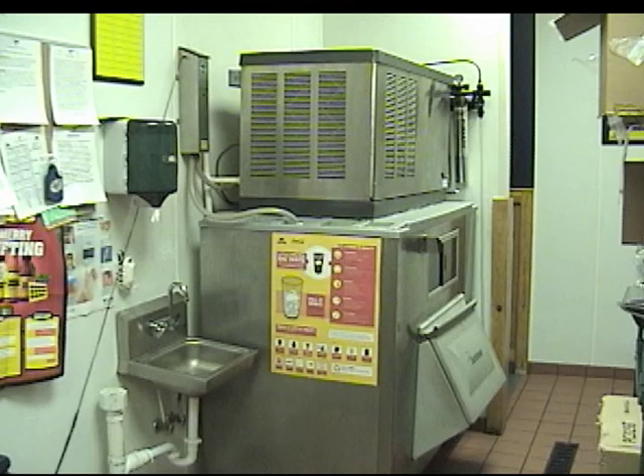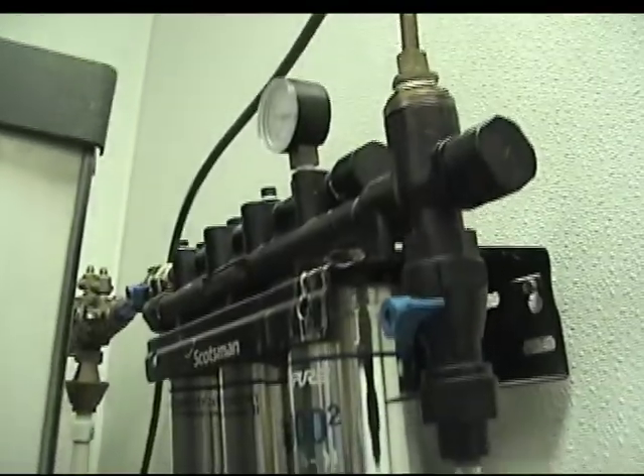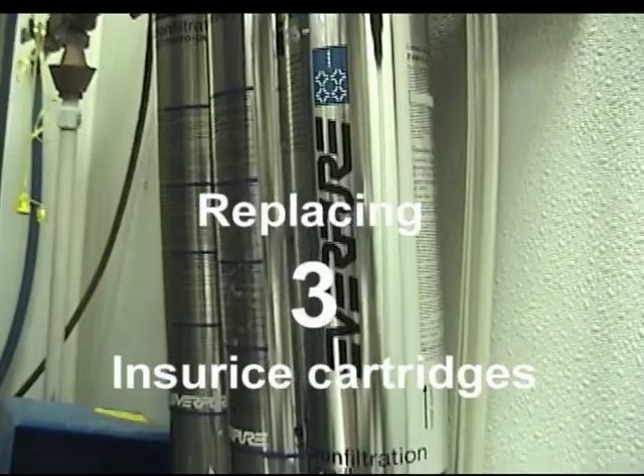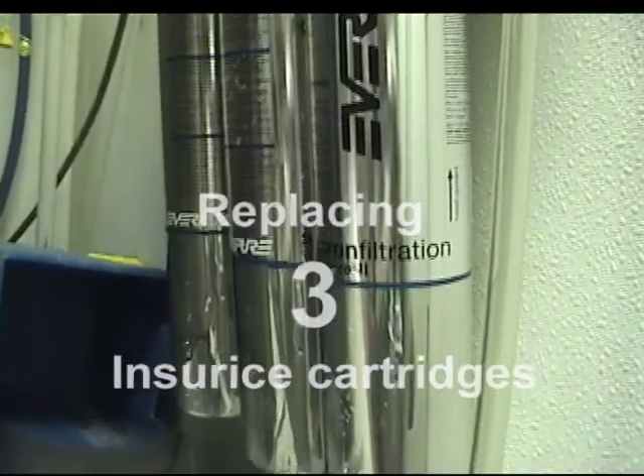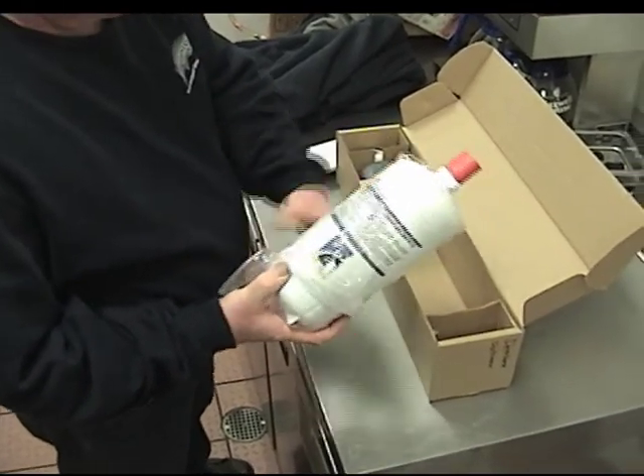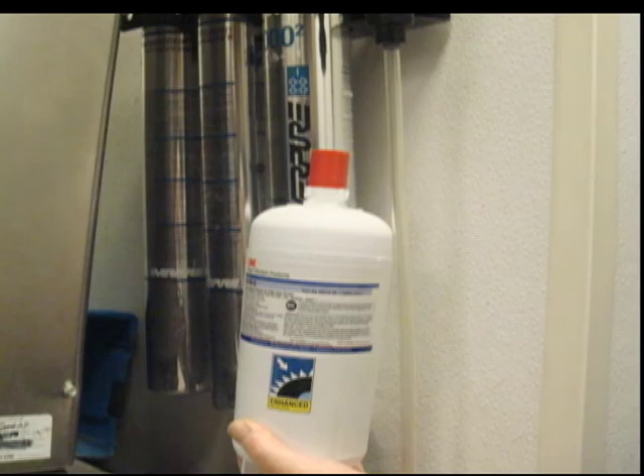We'll be installing a Cuno Ice Series water filter system onto a Scotsman Modular Cuber Commercial Ice Maker. A single Cuno Ice Series cartridge will replace these three Insurice filters. The Model 140S cartridge can handle up to 1,100 pounds of daily ice production, filtering 200 gallons of water at a flow rate of 2.7 gallons per minute.